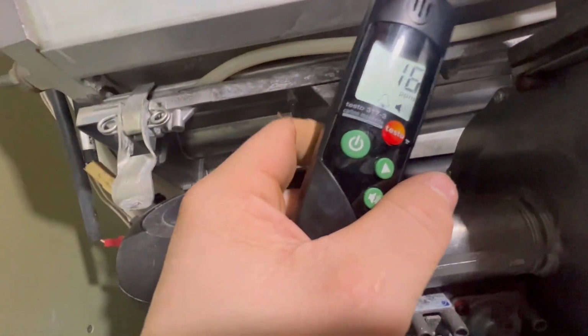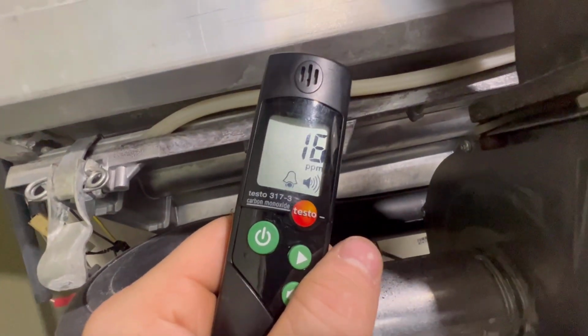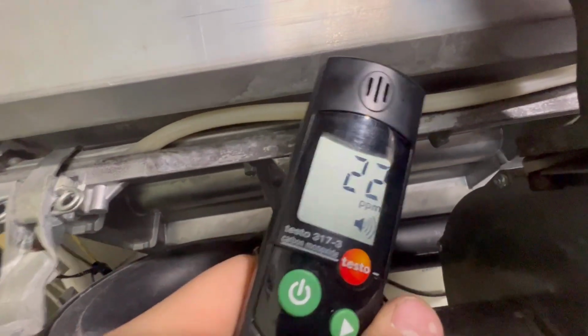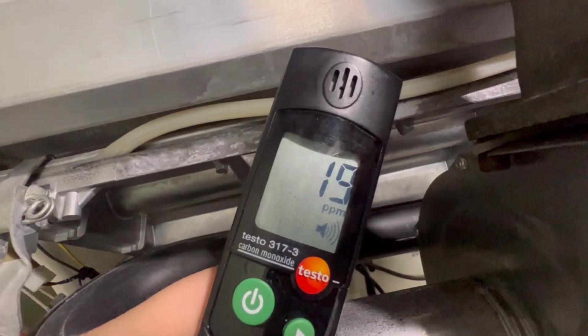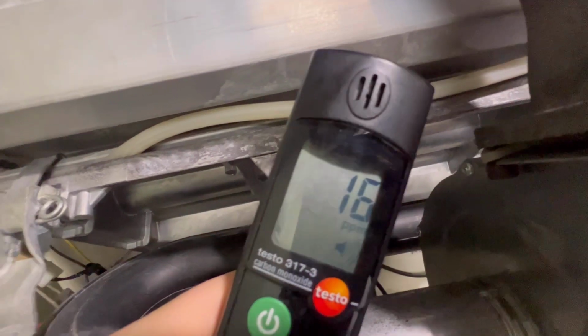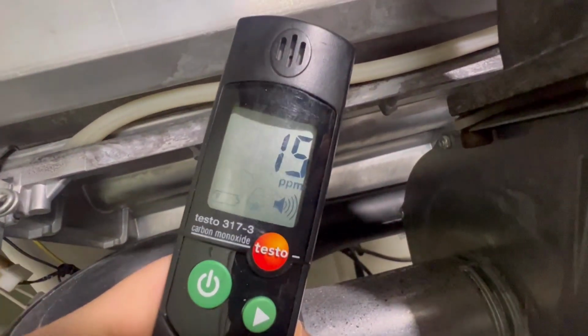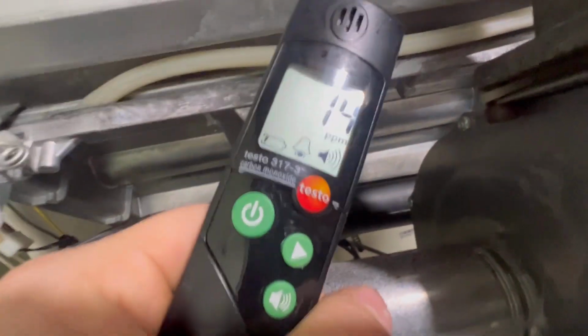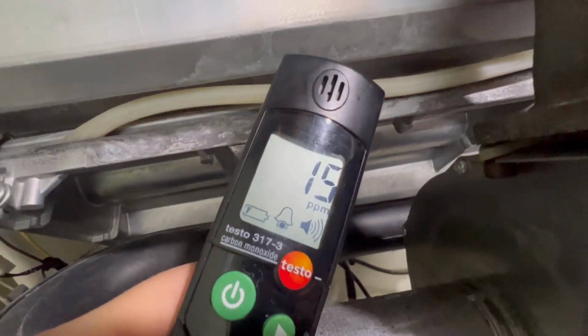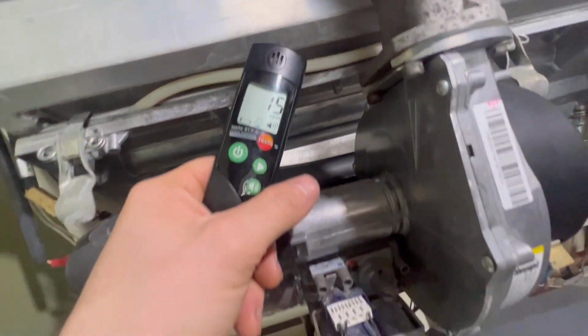I knew that was no good once I saw that gasket there. So I don't know if Christian wants to get somebody back here, whoever did this, but you're leaking carbon monoxide inside the cabinet, and I don't want to say that's throwing off the error code, but that's lessening the lifespan of it, and you're breathing in carbon monoxide. Yeah, you're breathing in carbon monoxide. Do you have a carbon monoxide detector in here?